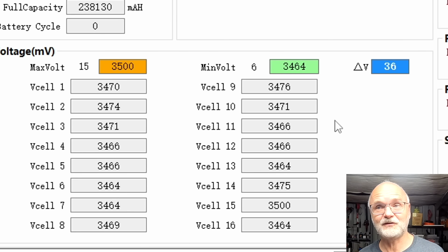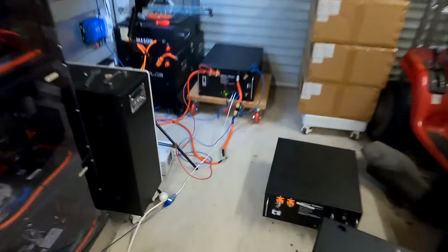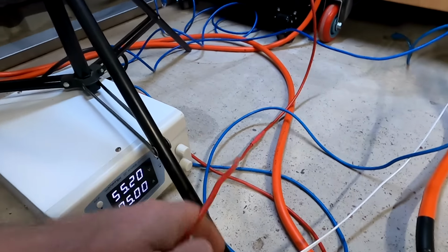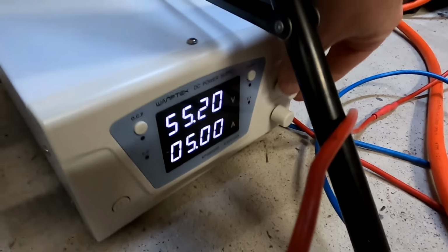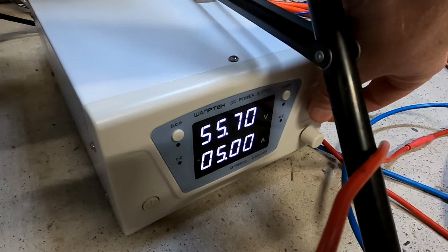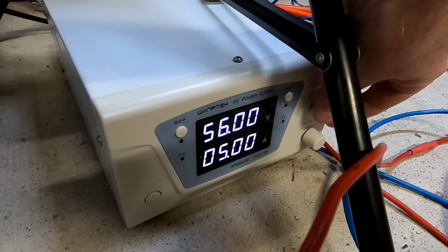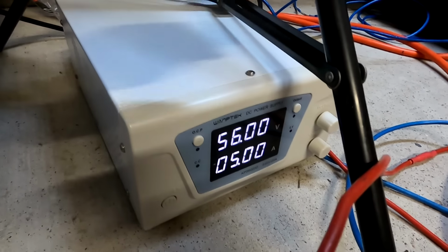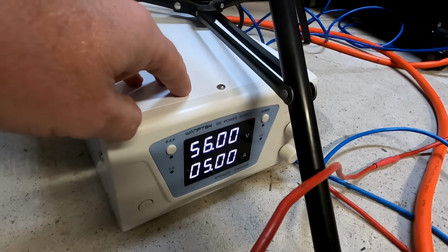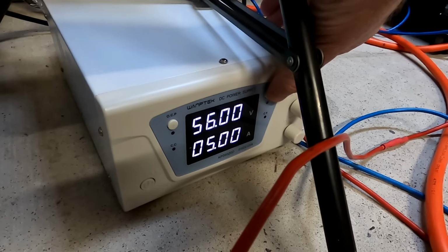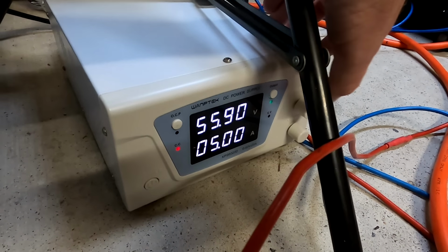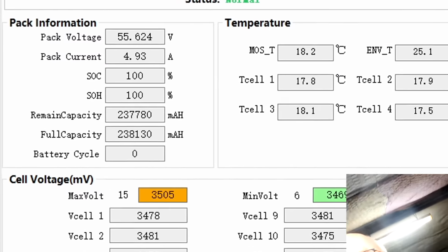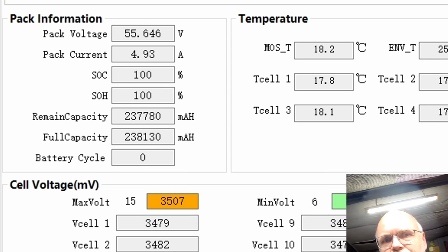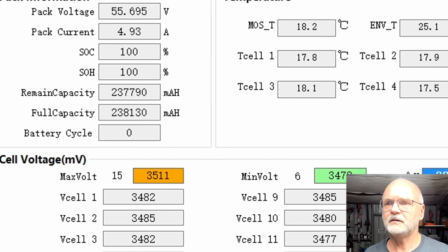That is really good, and I want to push this a little bit more. Let's see what happens if we go a little bit higher with the voltage. I have already attached my power supply. If we change this, say, to 56 volts, which is then 3.5 per cell, and turn this on, we should see around 5 amps going into the battery, and the voltage is now rising.